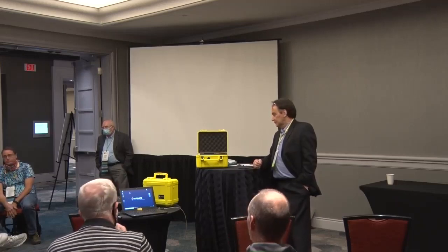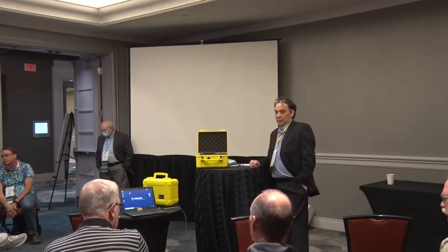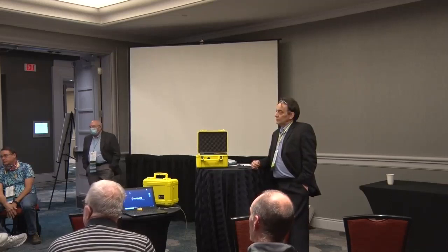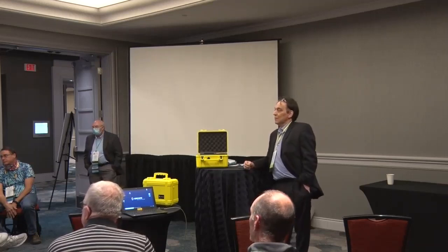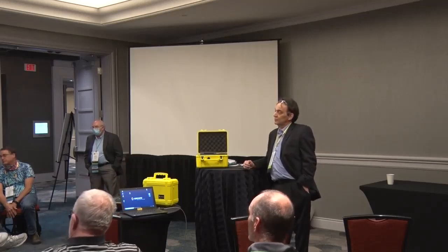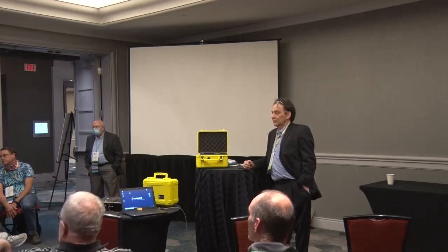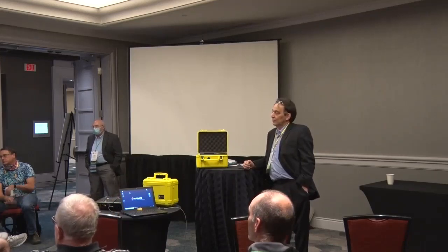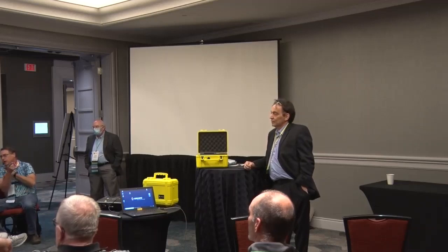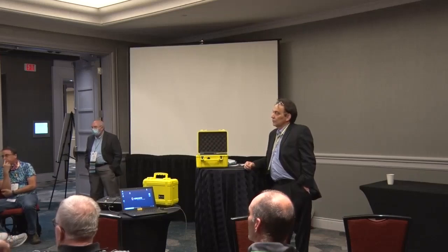The key is that if you're doing post-mitigation testing and you vacuum under the floor, you have to be careful on the timing. Because what you're doing is filling the cell for 90 seconds, and then you need to immediately disconnect, so the suction on the floor doesn't back-suck fresh air through the chamber, if you're trying to actually measure what's under the floor. Then let it sit for the 300 seconds without any change, any flushing out of the cell, so that the algorithm can see the loss of thoron in that chamber, and then it gives you both readings. You get thoron and radon at the same time.